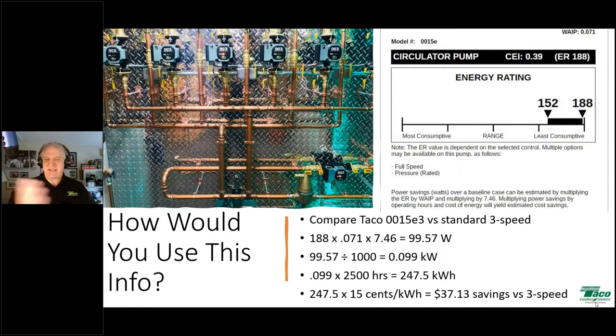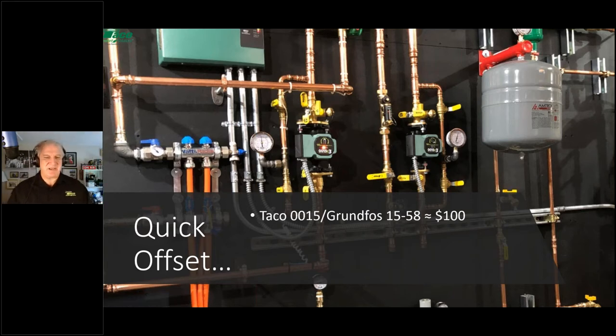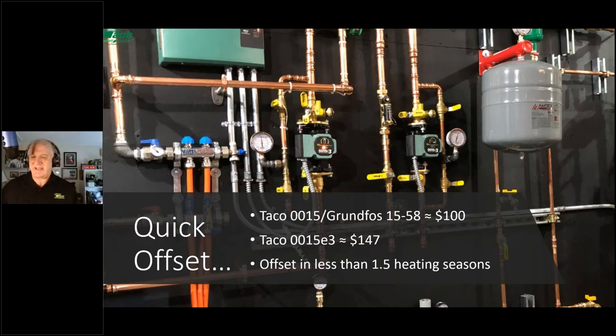All you have to do is say: here's the cost of this circulator versus that one. How long before I offset that increased purchase price? Comparing the TACO 0015E3 — around $147 online — to a standard three-speed circulator like the TACO 0015 or Grundfos 15-58 at around $100, you're looking at an offset in less than one and a half heating seasons. Not bad at all.